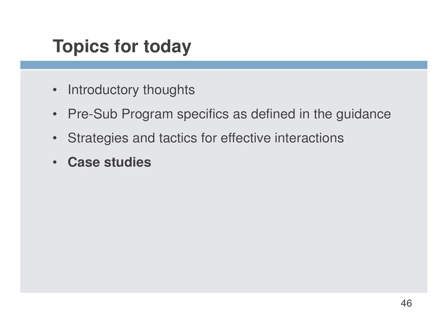Can we use the pre-sub to design the clinical study? I think the answer to that question is yes. If you have a big question, clinical studies are massive. An IDE is when you actually get the formal approval. But again, if it's complicated, you may want to use the pre-sub. Now the problem becomes the pre-sub has a feedback time frame of 75 to 90 days, and it's still informal. Whereas an IDE has 30 days, and now whatever FDA says is potentially appealable.